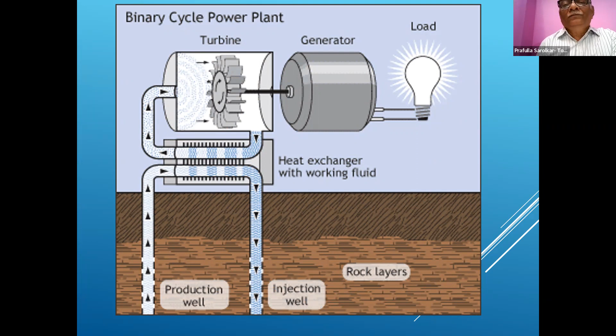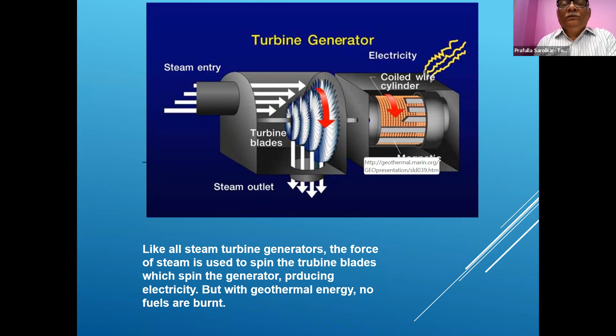This is a turbine generator. Whenever temperatures are higher, 250 degrees centigrade or more than 200 degrees centigrade, the steam is separated from the water, and then that steam is directly utilized just like a normal steam turbine or steam-based power plant to run the turbine. In this particular case, because we are using direct steam at a high pressure, 9 to 10 bars, or maybe sometimes even more, the efficiency of this steam-based power plant is more, and it has comparatively more economical advantage also.